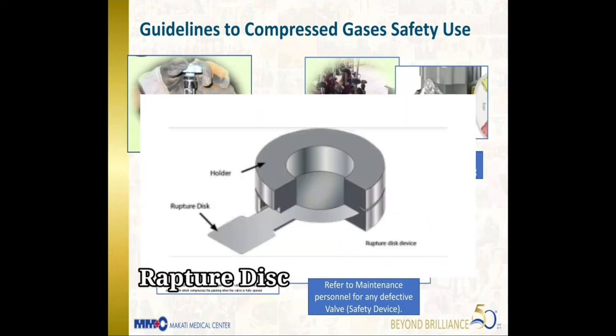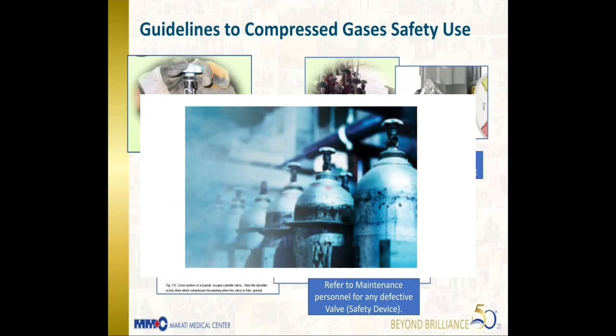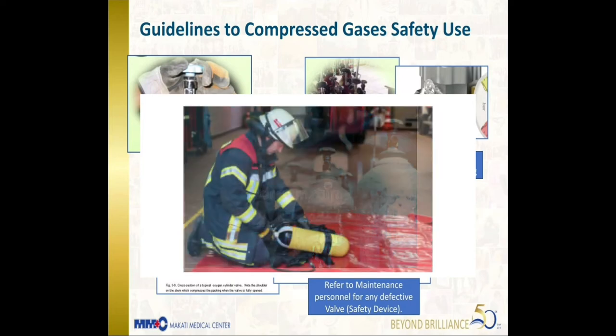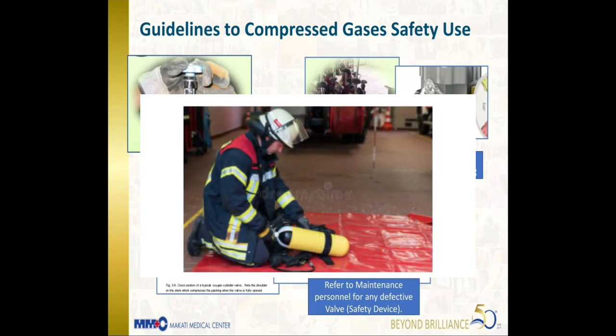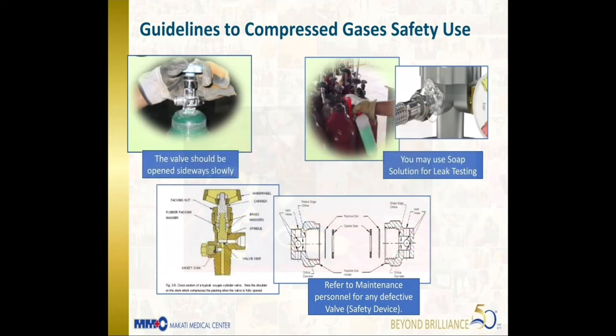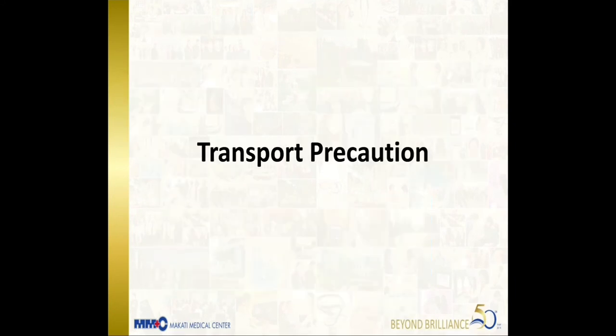Medical gas cylinders are equipped with a safety device called a rupture disc. This will burst or rupture to release gas when the cylinder's test pressure inside is reached. This is to prevent the cylinders from exploding, becoming a projectile, and causing injuries.